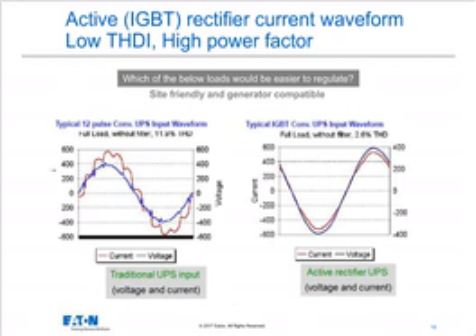So the waveform on the right shows what we do, we meaning most vendors now in the UPS arena. We use an active front end or an active rectifier. And what this does in short is it forces the UPS to draw its current in a sinusoidal wave shape rather than a highly distorted wave shape. We use pulse width modulated techniques in order to have the UPS draw current in many small sips as opposed to 6 or 12 big gulps per cycle.